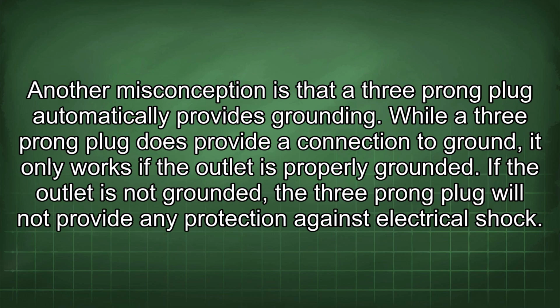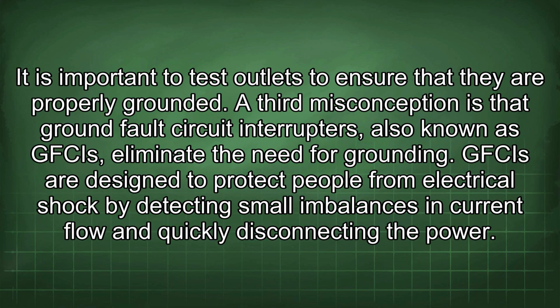Another misconception is that a 3-prong plug automatically provides grounding. While a 3-prong plug does provide a connection to ground, it only works if the outlet is properly grounded. If the outlet is not grounded, the 3-prong plug will not provide any protection against electrical shock. It is important to test outlets to ensure that they are properly grounded.